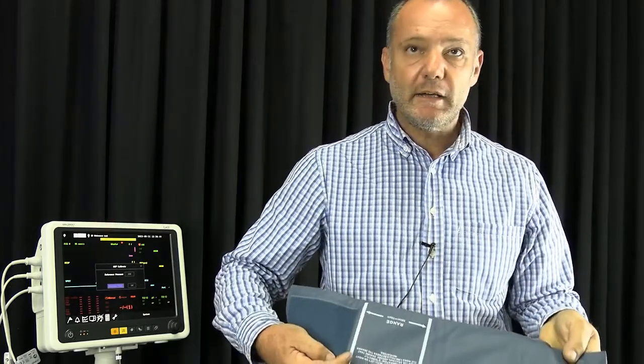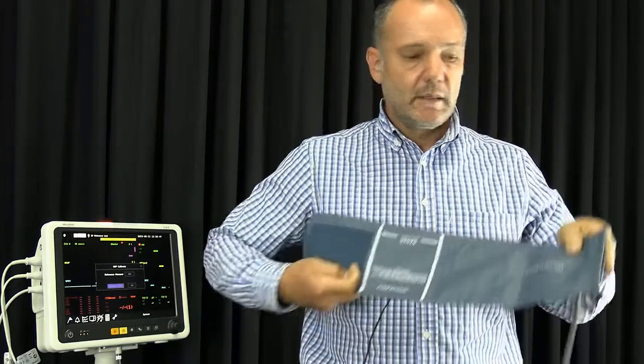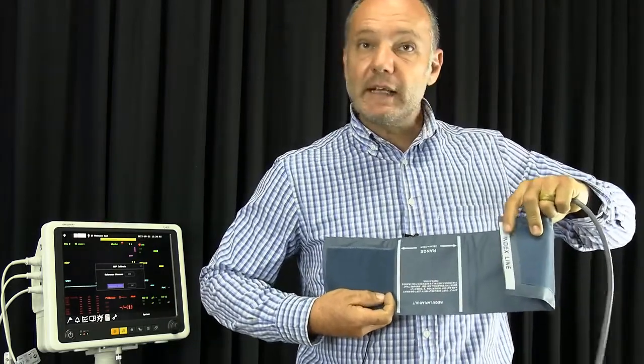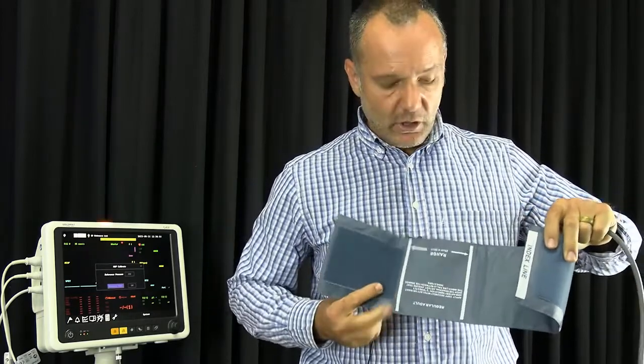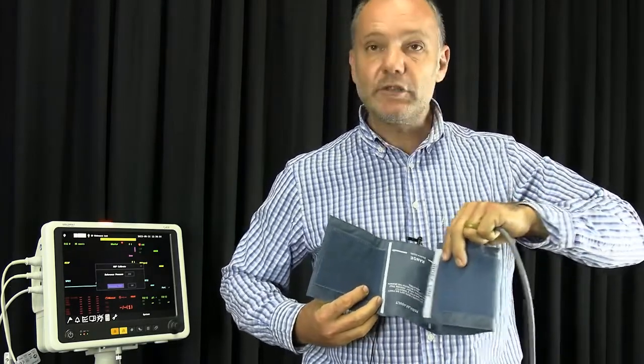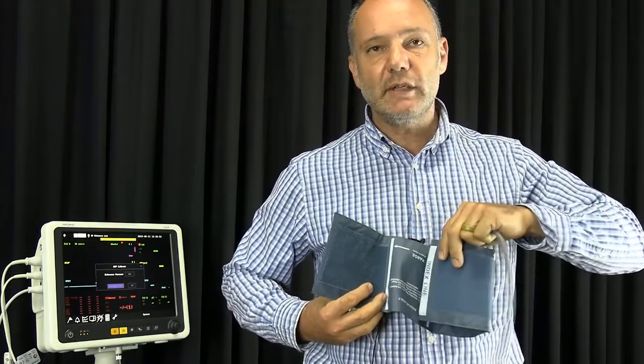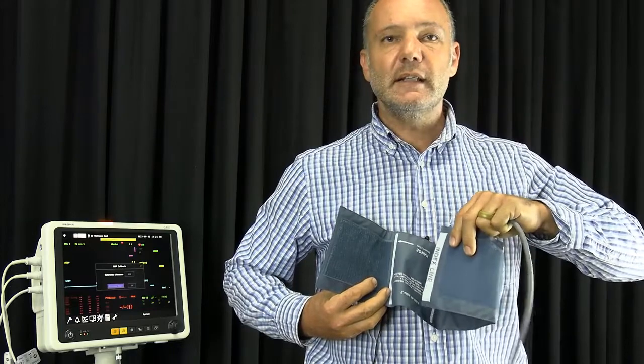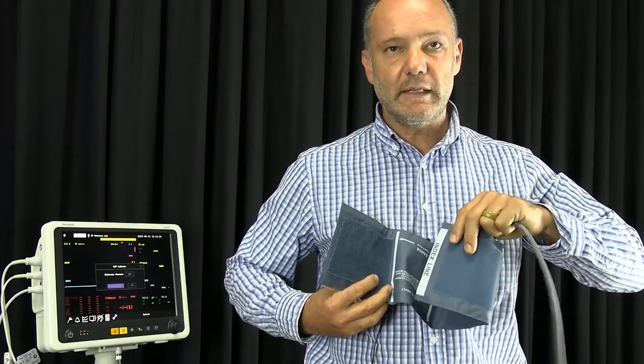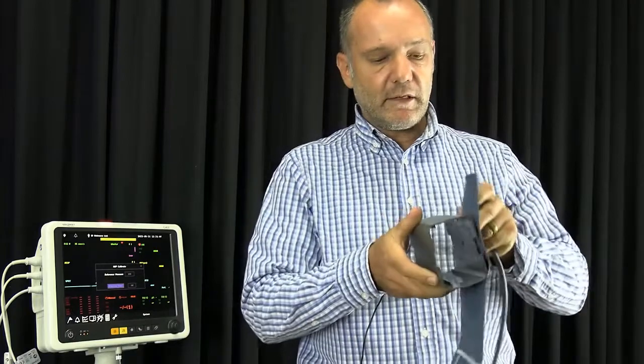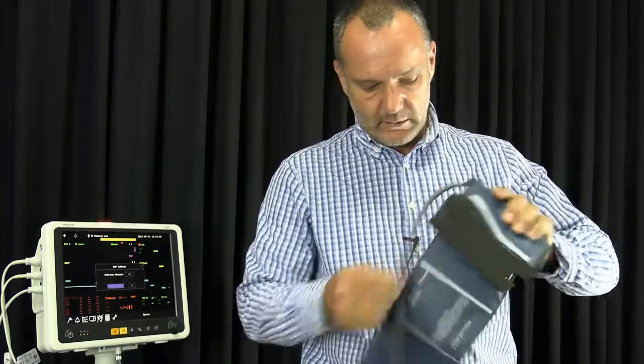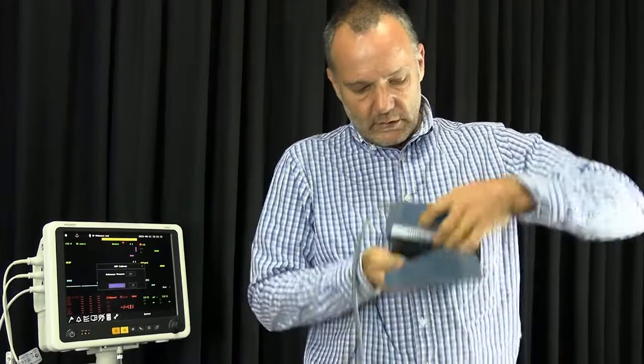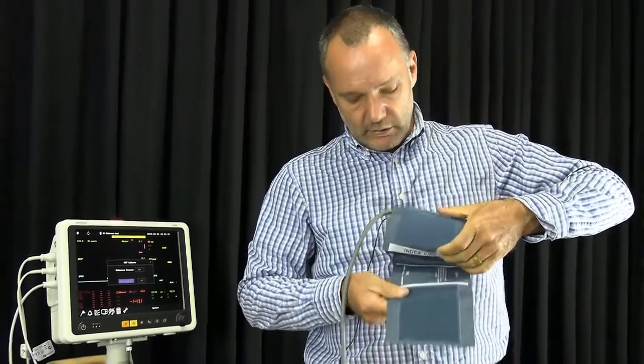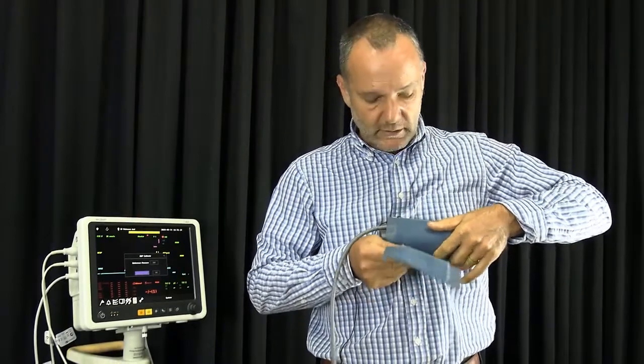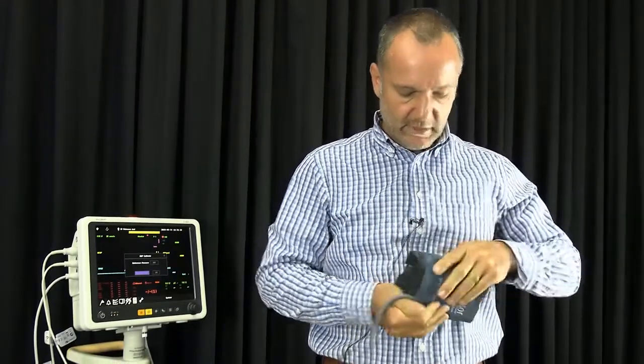When we look at a blood pressure cuff, you'll notice that we have two white lines here, and on this side we have an index line. So whenever I put it around an arm or a mandrel, the index line has to be somewhere between these two lines to make sure that it's the correct size of cuff. Otherwise, that is going to influence your readings at the end of the day. So the cuff of the mandrel I've selected, you can see the index line goes between those two lines. So I make sure that I've got the correct size of mandrel and the correct size of cuff.